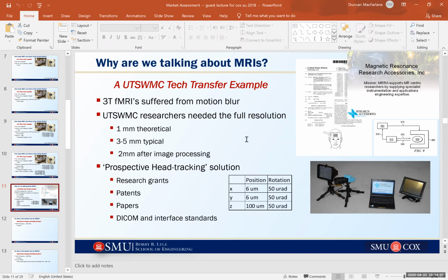What we were doing was we would have a fast camera with some filtering and signal processing. Remember, we've been talking a lot about that. We processed the images very quickly at the camera so that we could measure the movement, and then we could feed that signal back into the magnet in a prospective manner, so that the magnetic field and the electric fields would ride along with the motion.